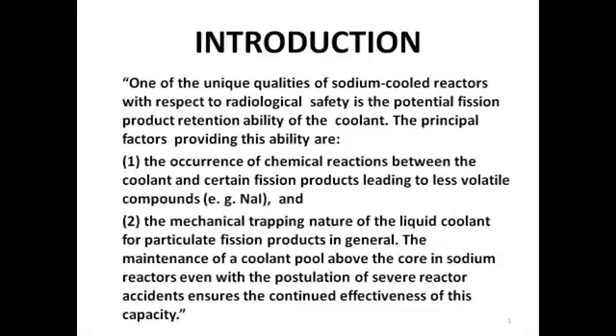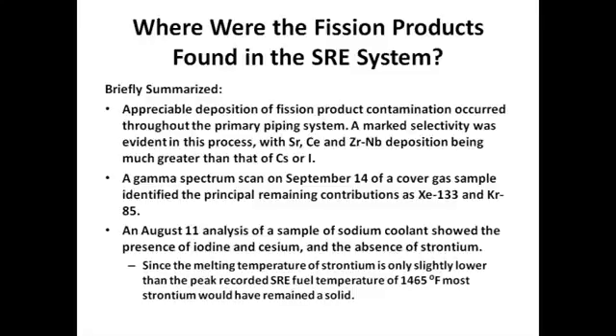The document contains this introduction, which is important to help explain why the fission products behaved as they did: one of the unique qualities of the sodium-cooled reactors, with respect to radiological safety, is the potential fission product retention ability of the coolant. Principal factors providing this ability are the occurrence of chemical reactions between the coolant and certain fission products leading to less volatile compounds such as sodium iodide, and the mechanical trapping nature of the liquid coolant for particulate fission products in general. Maintenance of a coolant pool above the core in sodium reactors, even with the postulation of severe reactor accidents, ensures the continued effectiveness of this capacity. Where were the fission products found in the SRE system? Briefly summarized, there was appreciable deposition of fission product contamination throughout the primary system. Marked selectivity was evident in this process, with strontium, cerium, and niobium-zirconium deposition being much greater than that of cesium or iodine. A gamma-spectrum scan on September 14th of a cover gas sample identified the principal remaining contributions as xenon-133 and krypton-85.